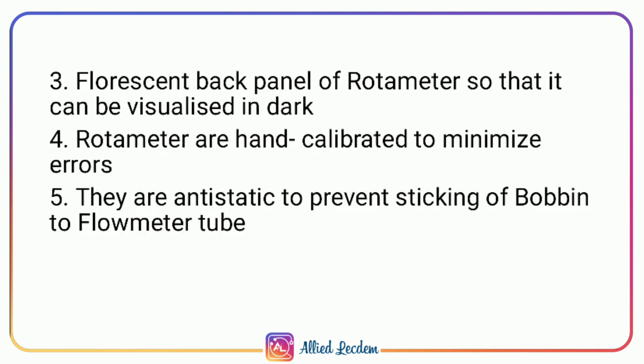Additional rotameter safety features include a fluorescent back panel so that the flowmeter is visible even in the dark, hand calibration of rotameters to minimize errors, and anti-static tubes to prevent sticking of bobbins to the flowmeter tubes.